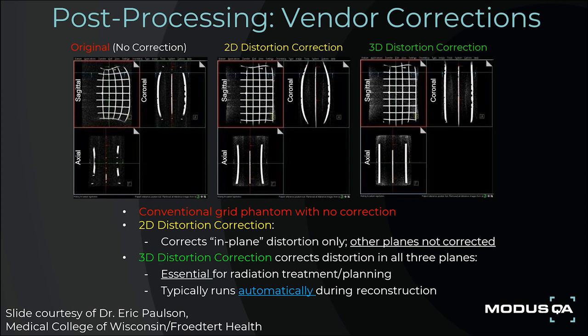Gradient coil designers use harmonic analysis methods, among other field target techniques, to design gradient coils. The requirement for large diameter, short length bores confounds perfect gradient linearity, necessitating the use of spherical harmonic-based 2D and 3D image correction to gradient nonlinearities for all MR manufacturers.